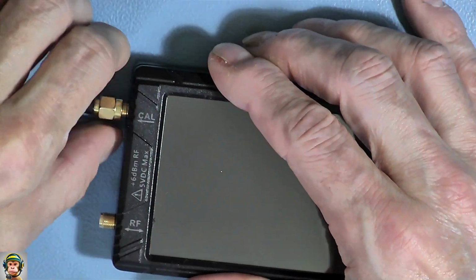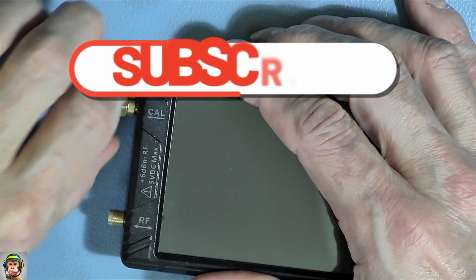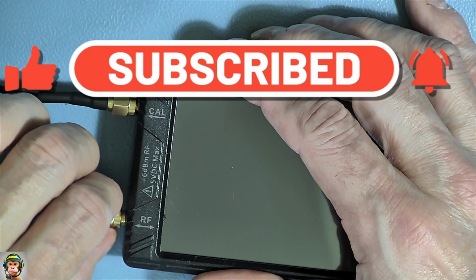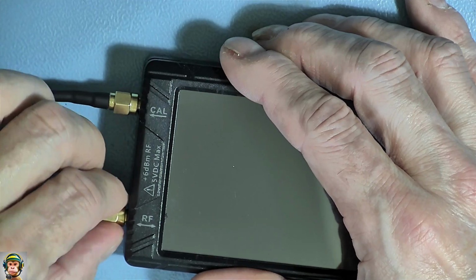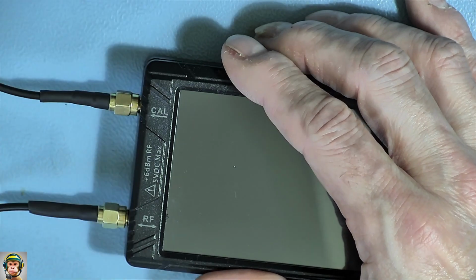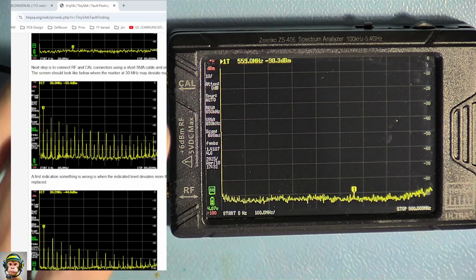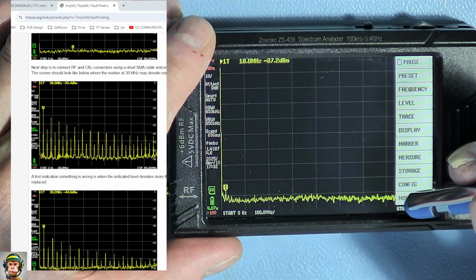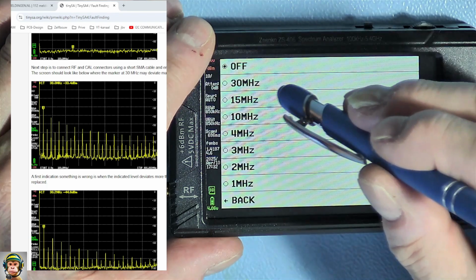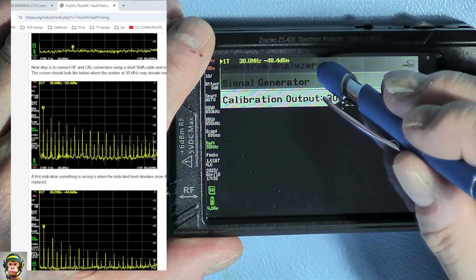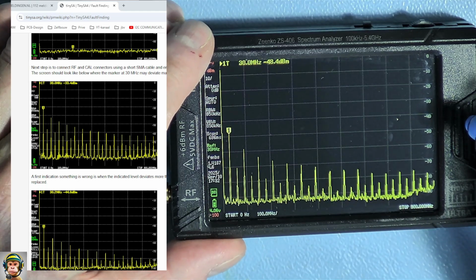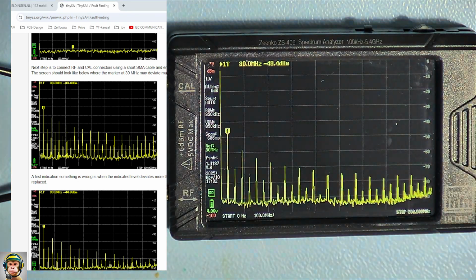For the next test you have to connect the RF and cal connectors using a short SMA cable. Make sure you tighten the connector properly. Now select Mode, Calibration Output, 30 MHz and return to Spectrum Analyzer mode. The screen looks like this. The marker at 30 MHz should be at -35 dBm with a maximum deviation of 4 dBm.